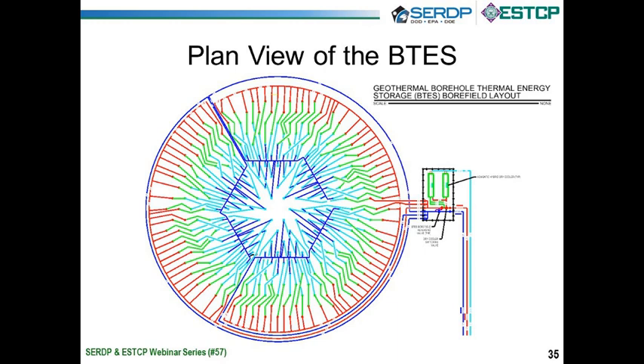So cold in the middle, charging, warm water heading back to the building to either heat the building or be dumped to atmosphere through the dry coolers. In the summertime, warm water flows to the perimeter. Those boreholes on the perimeter are great because they're exposed to infinity, so they have a good ability to dissipate heat. And then as they work their way to the inner sanctum there, the cold water gets colder and goes back to the building. So that's a plan view of the BTES at Albany.